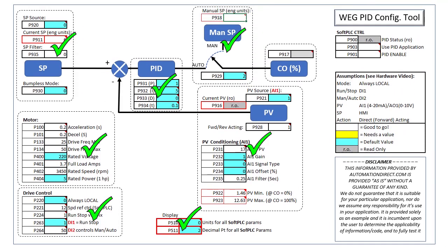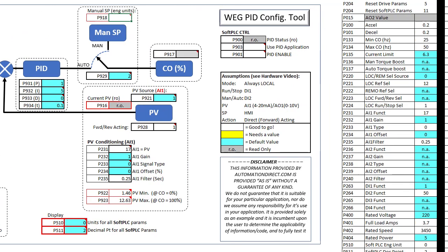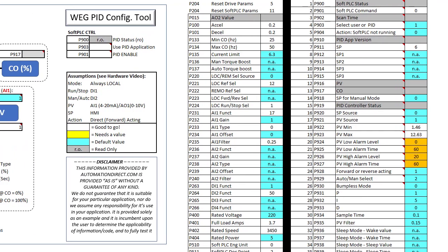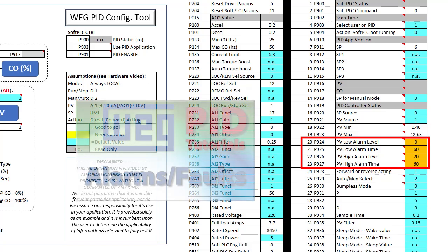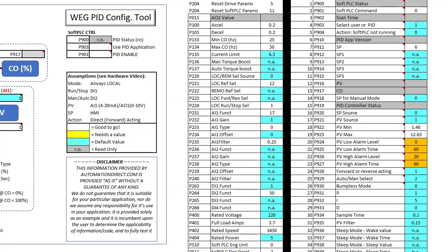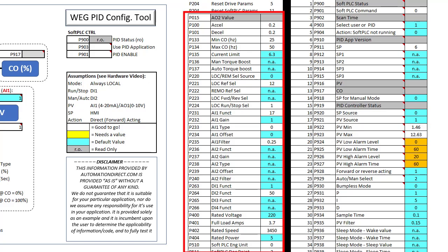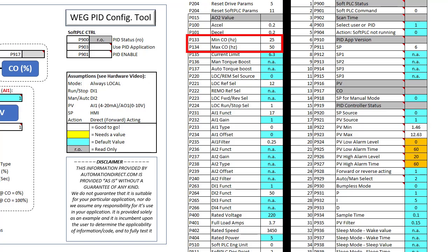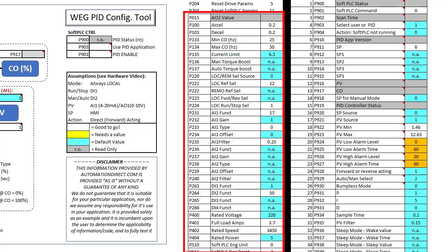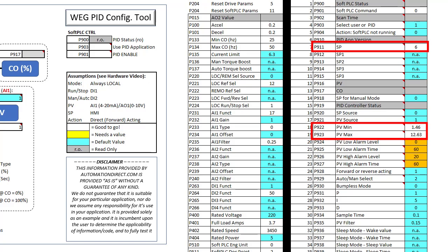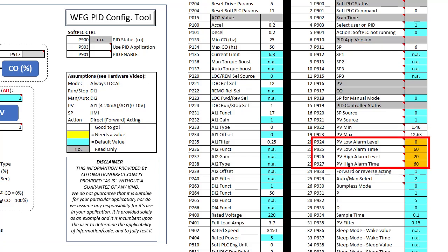We have gotten rid of all the yellow cells so we are ready to give this a try. Over here is a list of all of the PID related parameters in numerical order which makes entering them into the drive super easy. We are not covering alarms in this video so I just entered some values that will prevent alarms and faults. There is a whole separate video about how to use alarms and faults if you want to use those. Since all of the blue parameters are defaults, we don't need to change those and the gray parameters are ones we aren't using and most of these we set up in the previous video, all we really have to do is enter the new min and max drive frequencies and verify the rest of what we think they should be, enter just the three PID parameters and modify these four alarm parameters so they don't interfere with this demo. I'll go ahead and enter all of the new parameters into this drive and verify all the rest.